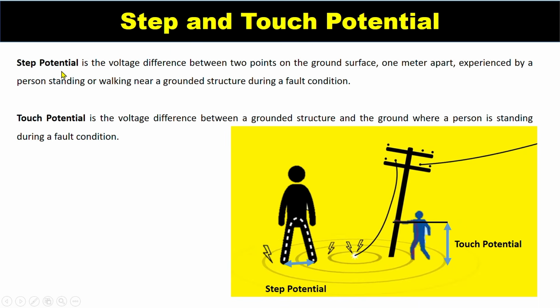Now when we design the earth mat, we say our earth mat is okay or not based on the step potential and touch potential. Step potential is the voltage difference between two points on the ground surface 1 meter apart, experienced by a person standing or walking near a grounded structure during a fault. This is the condition you can see here.